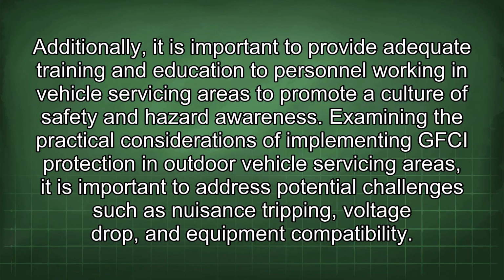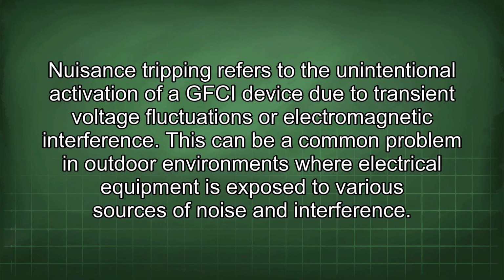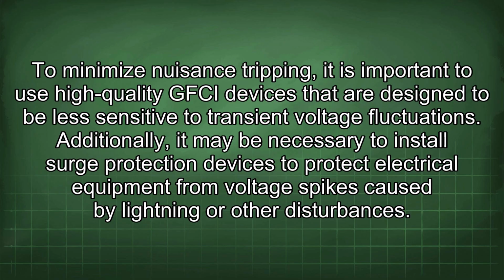Examining the practical considerations of implementing GFCI protection in outdoor vehicle servicing areas, it is important to address potential challenges such as nuisance tripping, voltage drop, and equipment compatibility. Nuisance tripping refers to the unintentional activation of a GFCI device due to transient voltage fluctuations or electromagnetic interference. This can be a common problem in outdoor environments where electrical equipment is exposed to various sources of noise and interference. To minimize nuisance tripping, it is important to use high-quality GFCI devices that are designed to be less sensitive to transient voltage fluctuations. Additionally, it may be necessary to install surge protection devices to protect electrical equipment from voltage spikes caused by lightning or other disturbances.